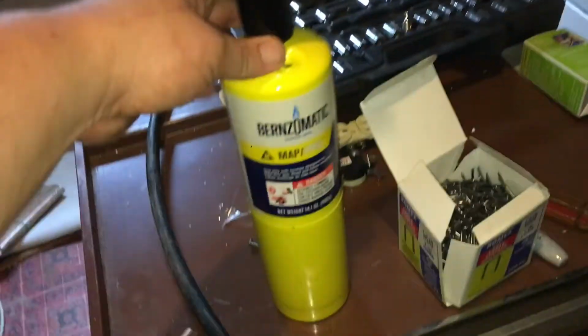I've got my MAP gas torch here, Stay Bright 8 solder, and Stay Clean flux to flux this up with. Here's my little jug of 407C, my gauge set, liquid line filter dryer, and my 5 CFM Robinair vacuum pump. So I've got just about everything I need.